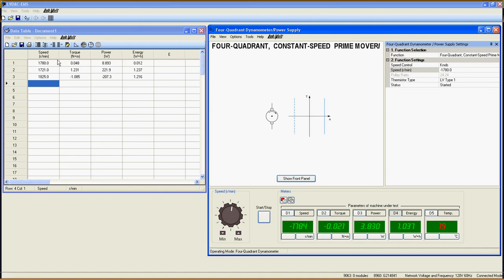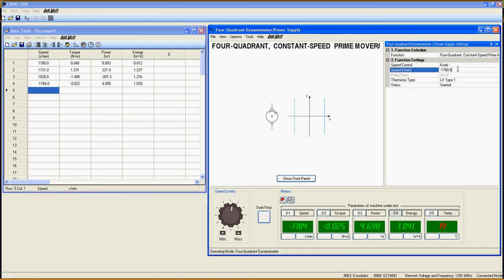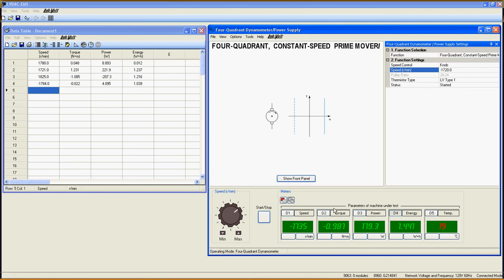As I decrease the speed to negative 1720 rpm, you can see that the power is positive again. The induction machine is now a motor, rotating counterclockwise, which implies that the prime mover is generating electrical power and is sending it directly into the power grid. Negative speed and negative torque proves that we are now operating in the third quadrant.